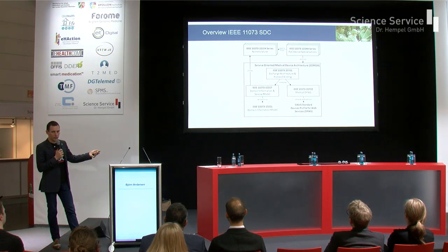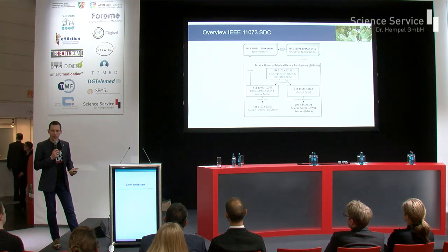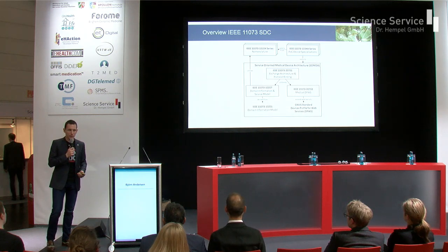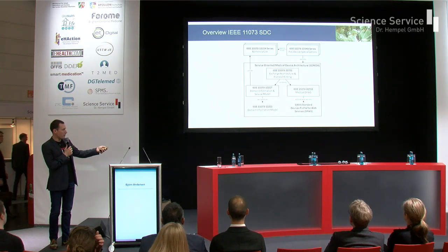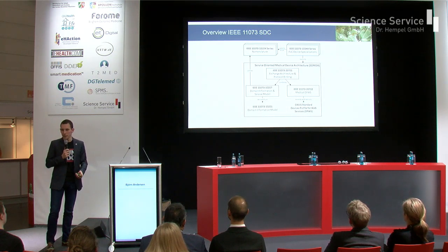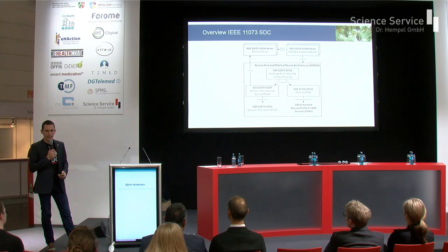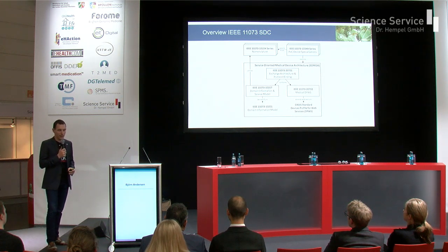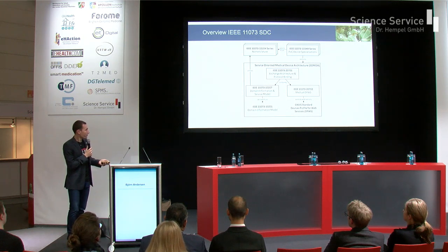Well, you don't have to touch the structure definition of the medical device domain information and service model. We even tried that. It is actually possible. We always told people it's possible, and now we gave proof that it actually is. So we used a different transport technology here, implemented a different binding, and it works. It's completely transparent to the library user. He still sees the model of his device and doesn't really understand what's happening below that, but that's okay. That's why we built it that way.